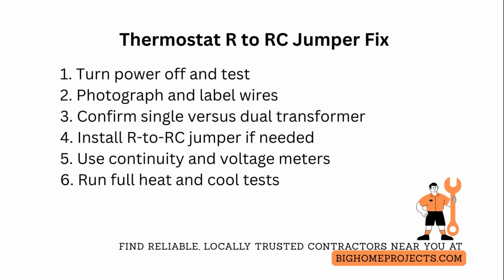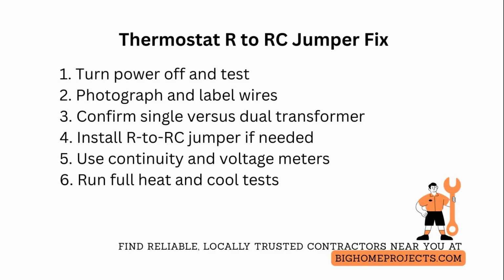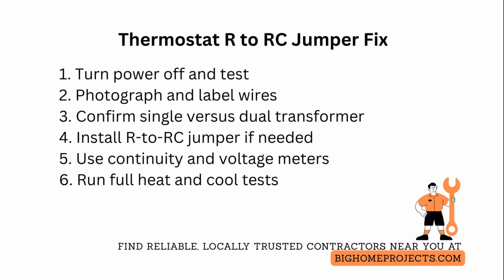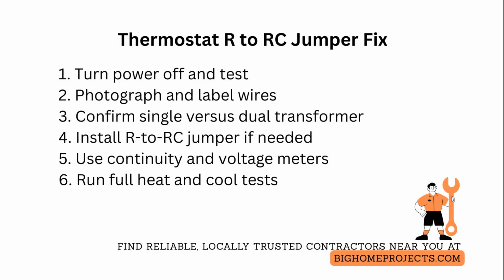Identify whether your system uses one transformer or separate transformers by checking for a single R wire or two distinct R and RC feeds at the control board. If you find only one red wire from the transformer, plan to install the jumper on the new thermostat. Use a continuity meter to verify the jumper connection after installation and run a full mode test.